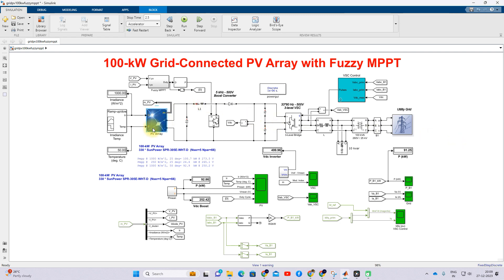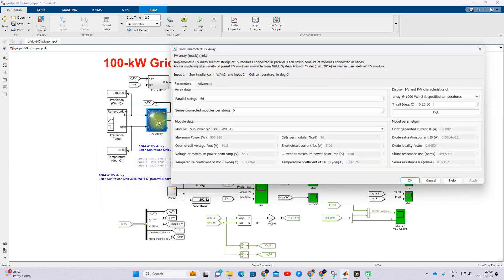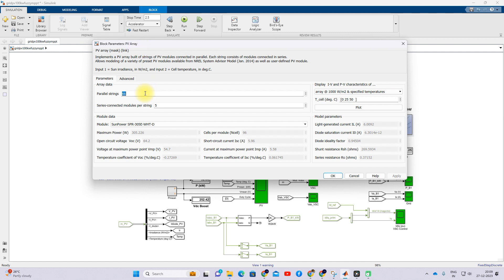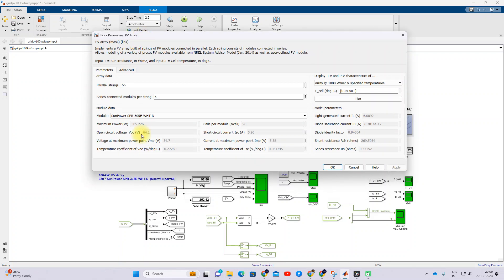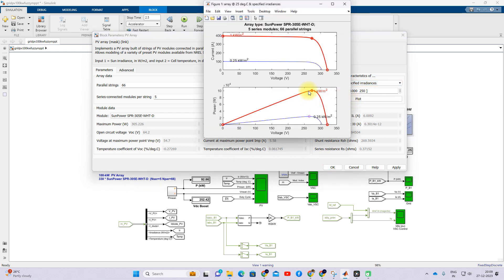The PV array has a panel rating of 305 watts. The number of series panels in each string is five, and the total parallel strings is 66. When you open this model you can see the rating - the maximum power is 305W per module, with five series-connected modules and 66 parallel strings, which can generate a maximum peak power of around 100.7 kilowatts at 1000 watts per meter square.